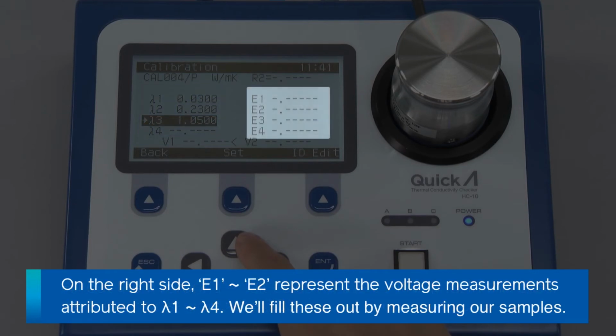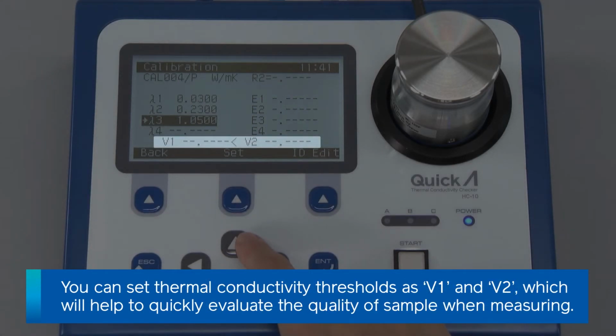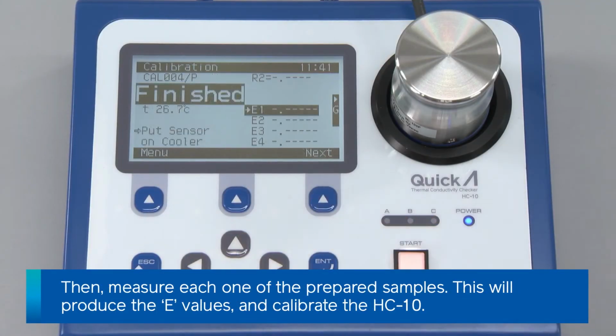You can see E1 to E4 on the right side of the screen, which are the voltage measurements attributed to lambda 1 through 4. We'll fill in those E values later by measuring the samples with the HC-10. At the bottom of the screen, you can also set thermal conductivity thresholds as V1 and V2, which will help quickly evaluate the quality of a sample during measurement. Once everything is filled out, press the Start button to begin calibration.